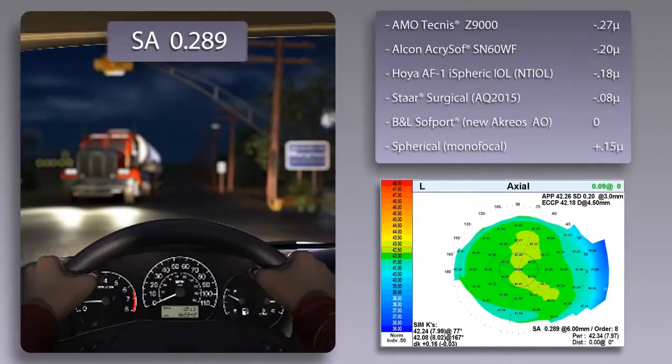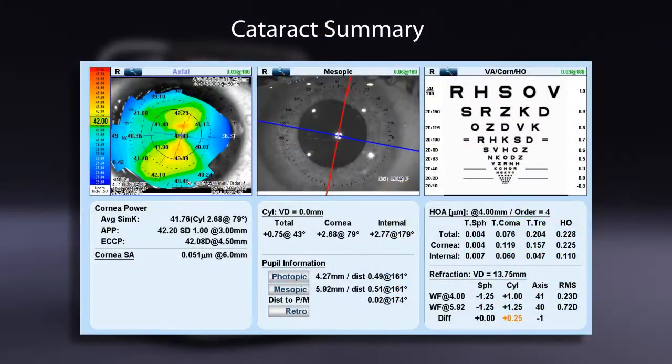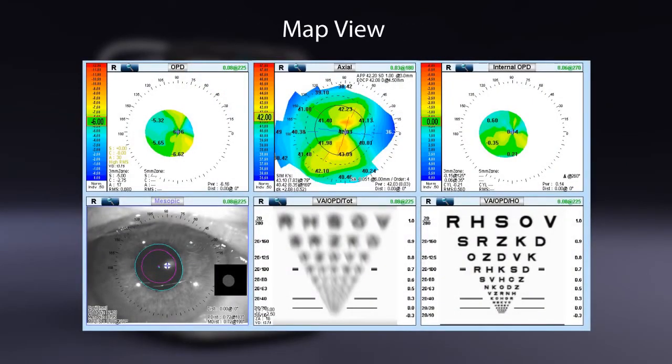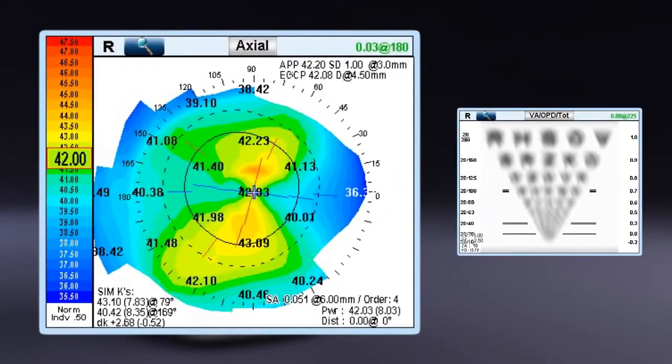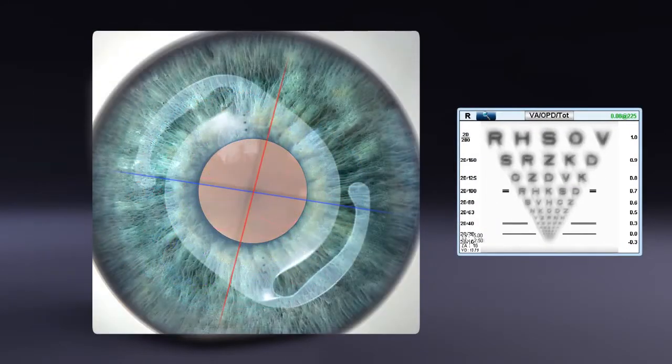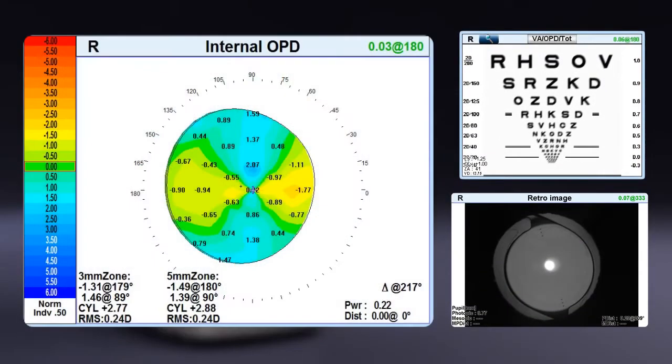IOL applications include spherical aberration of the cornea for aspheric IOL selection. Cataract summary displays any high-order aberrations that may remain after the cataract is extracted. Map view shows pre-op measurement with the ability to display the post-op measurements showing the correction along with the markings of the toric IOL in the retroillumination image and lens placement with the internal OPD map.